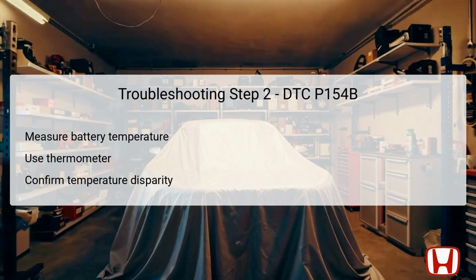Once the thermometer reading is taken, check the estimated battery temperature on the HDS. If there's a discrepancy of 41 degrees Fahrenheit, 23 degrees Celsius or more between the two measurements, this indicates that the sensor may be malfunctioning, and the battery sensor should be replaced. If measurements align, proceed to the next troubleshooting step.